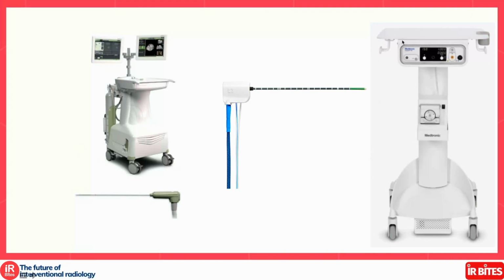On the right here, you have a much simpler system, which is the Covidien Emprint system. So this is the Covidien Emprint probe, and that's the NeuWave probe. On the Covidien Emprint system, you only have the ability to set the energy and time. That's about it. All the planning does not involve the system itself.